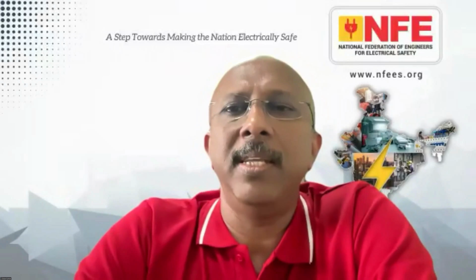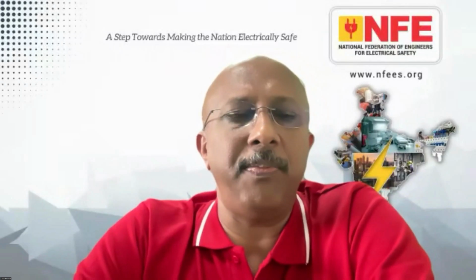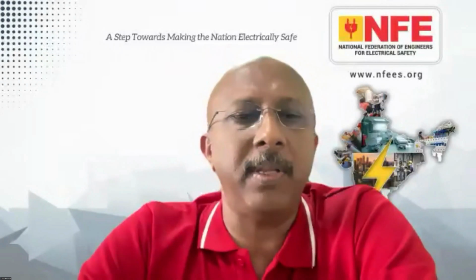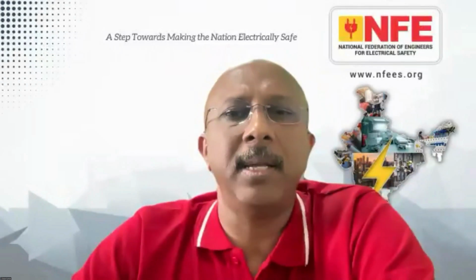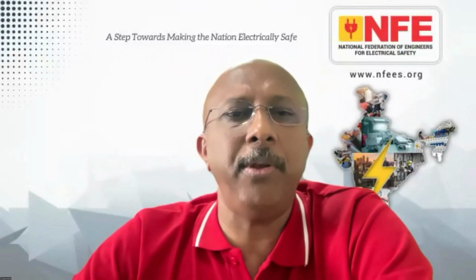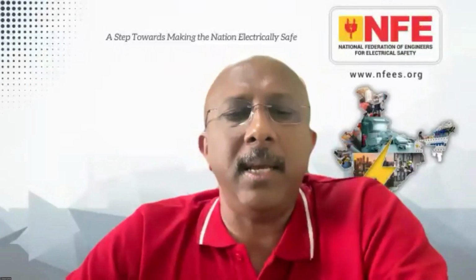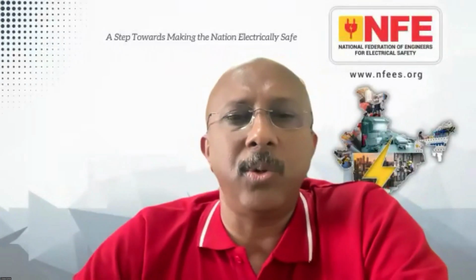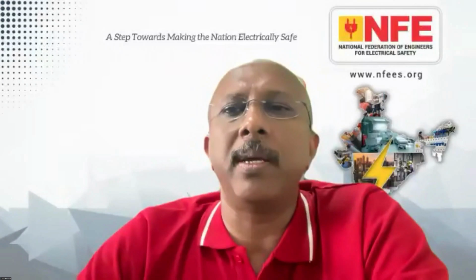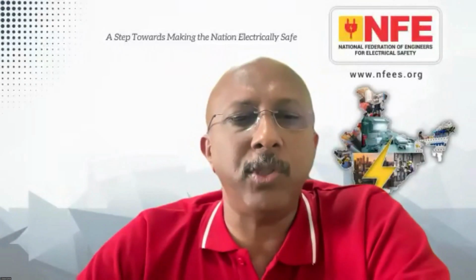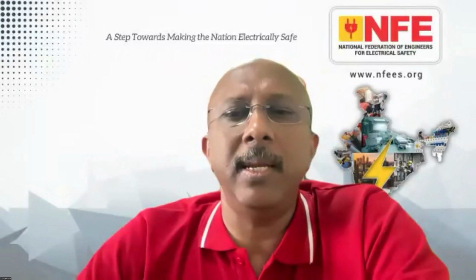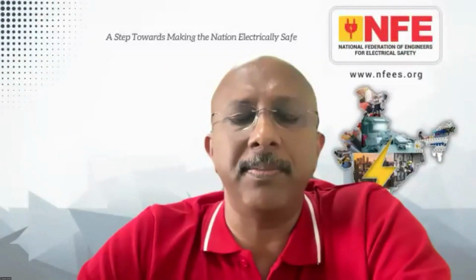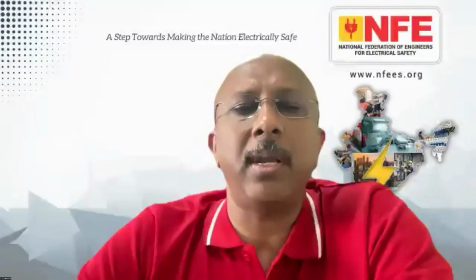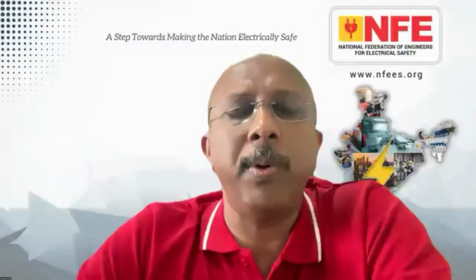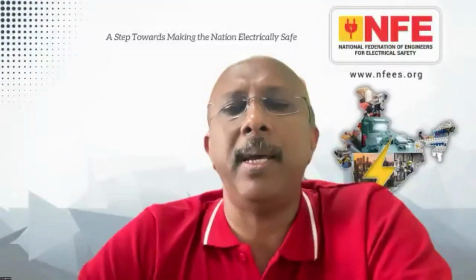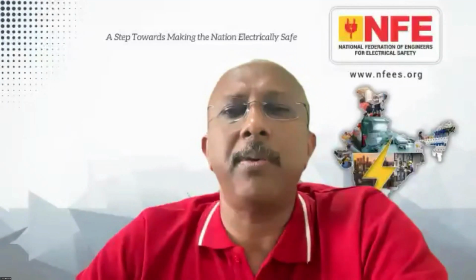Yeah, I can explain. It is by proper selection of materials and proper erection of the different electrical materials. Then you have to test it before using, and you have to periodically test it. So selection, erection, design, and verification. If you do these properly, of course, you get a very safe electrical installation. As I said, one of the big problems we see in the industry is oversized protective devices. People only talk about big short circuits, 25 kiloampere, 10 kiloampere, 30, 40. Nobody talks about the minimum current required to trip an MCB. So please look at the sizing of the protective device very carefully.